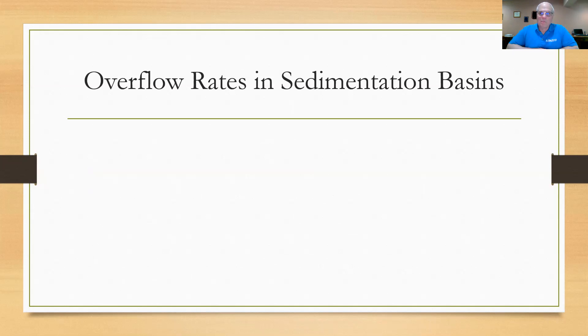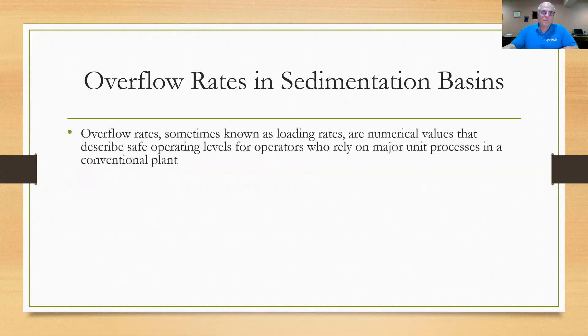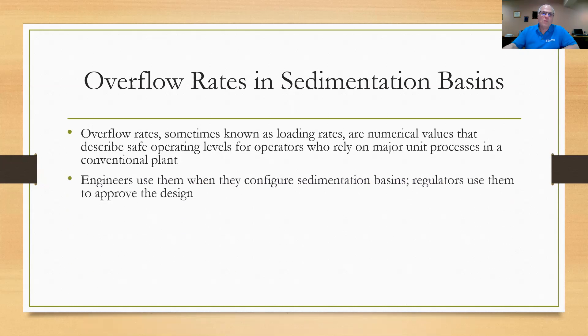We'll talk about overflow rates and sedimentation basins. Overflow rates, sometimes called loading rates, are simply numerical values that describe safe operating levels for operators. We're going to have surface overflow rates and weir overflow rates attached to our sedimentation basins that we should follow. When engineers design and configure sedimentation basins, they use these rates, and regulators use them to approve the design. As long as we stay within those parameters, we can operate it properly.